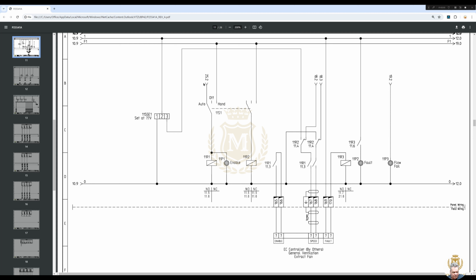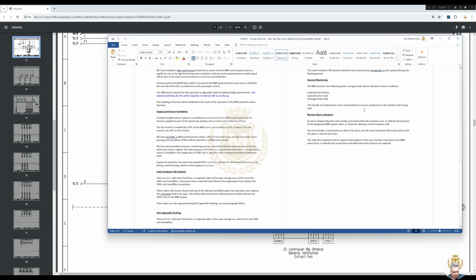But where is my, there's my auto, which is from the BMS energizing 11R1, which also puts that light on. 11R1, which is that for my enable, which is right. But what I can't see here is flow. And they definitely said in the des ops, fan inverters able to develop for you. A differential pressure switch is mounted across the fan to provide the flow proving. Any failure of flow will be reported to the BMS. So a differential pressure switch normally is just on and off, so it's a digital input. Well, there's no digital input.